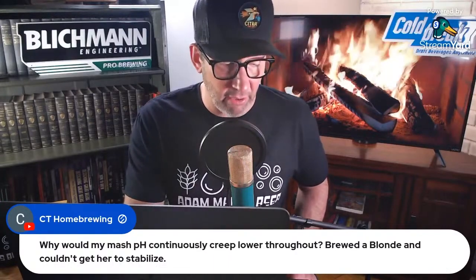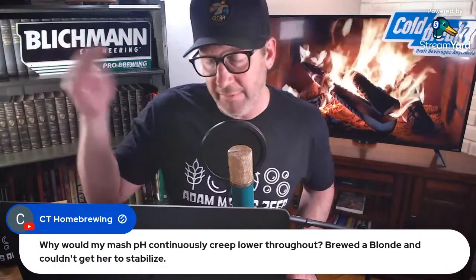Making sure that you're also taking the temperature of that sample to a uniform point. Typically, a lot of those instruments like to run around 60 F or whatever your baseline measurement is. Double check that too, because that could be a factor. He does a 3-point calibration, and it's a little high, 5.4 to 5.6 as mash continuous pH. That's a stumper, man. I don't know.